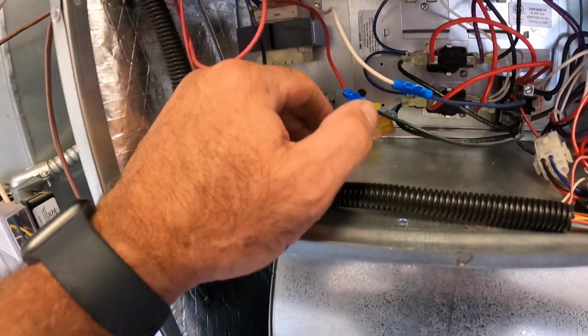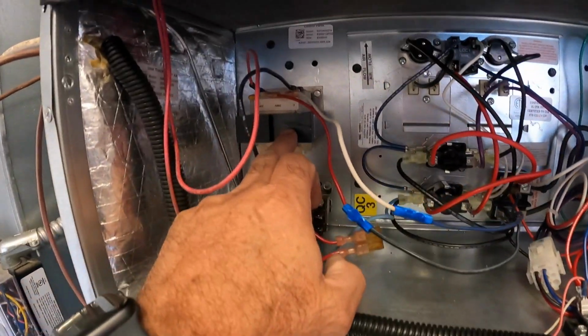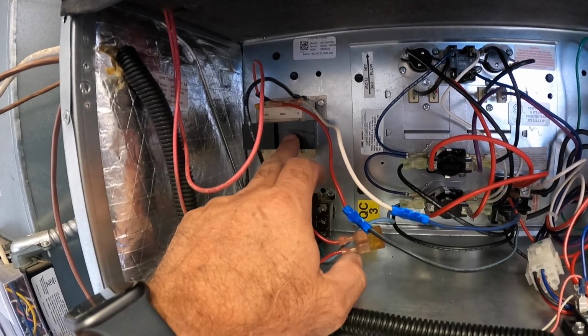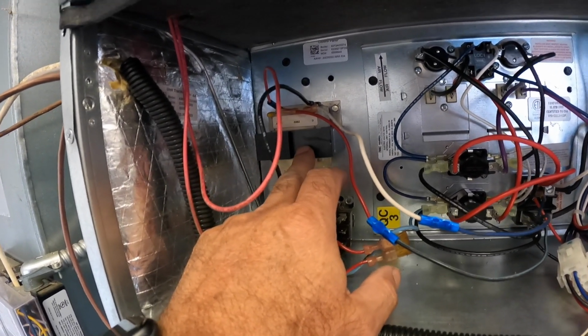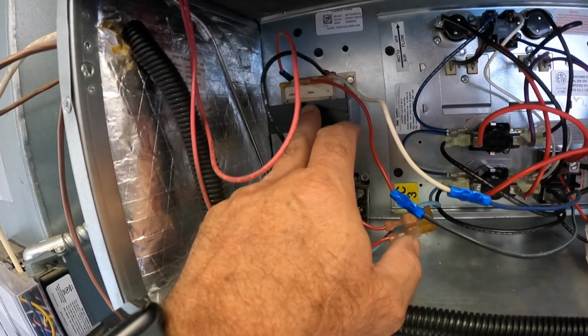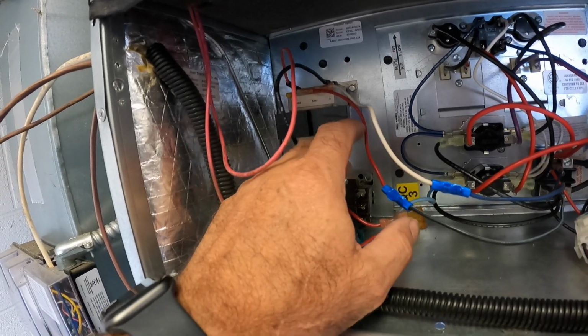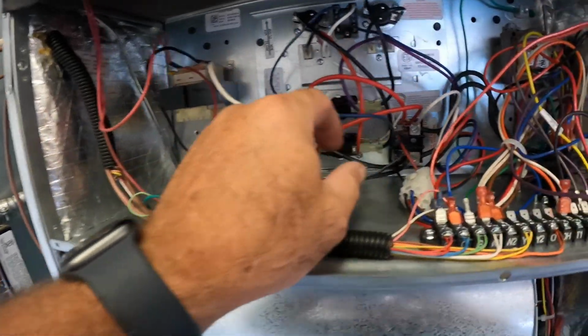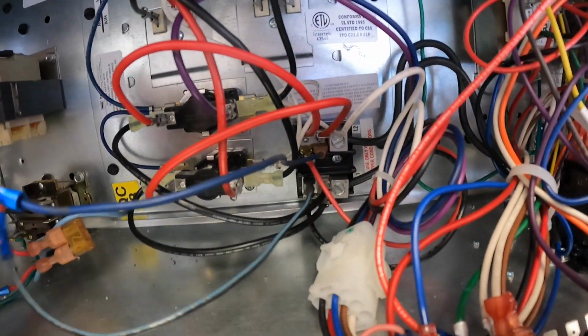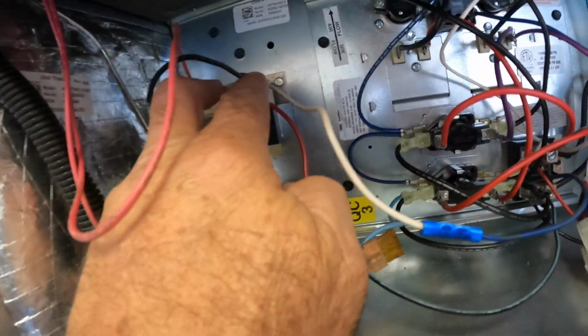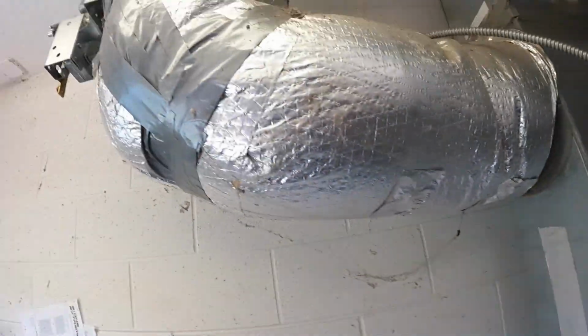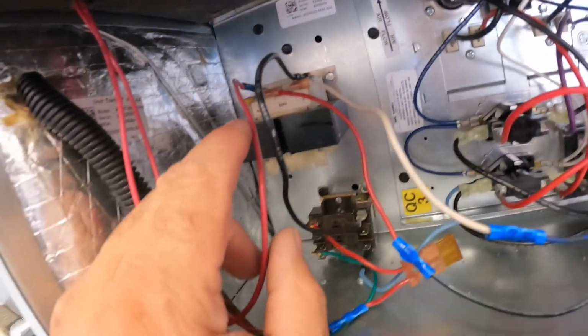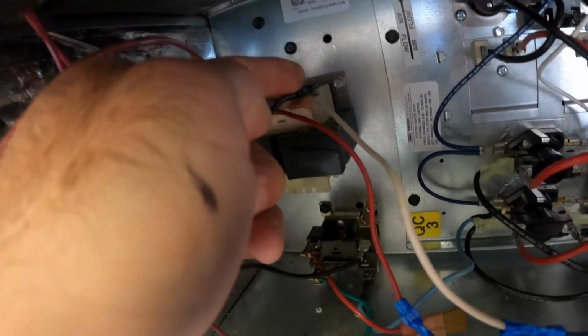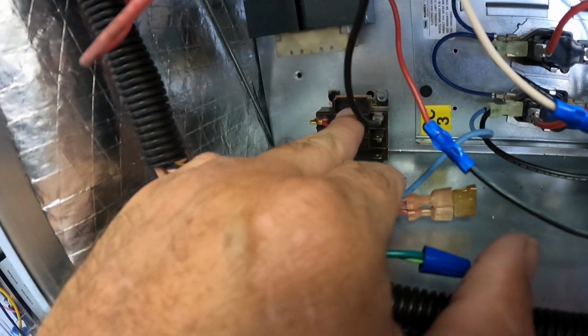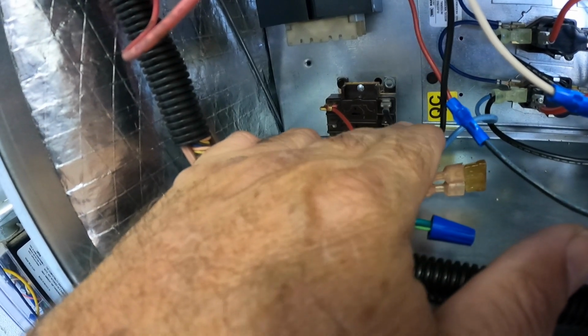Okay, I went ahead and finished up in here and got this fresh air damper rigged up. What I did, I took the control transformer out of the old Trane air handler, because it looked a lot better than that little one that Johnson Controls had put in there to start with that had never been used. It was already real rusty. So I just put it on over here. I had all this room. I tapped it off of my two main lugs, so I got 208 going into the 200 side of the primary here, and coming off of it, this one wire already had that crimped on terminal, so I just plugged it straight to the transformer on one side, and then I did a jumper from the other side of the transformer down to the fan relay out of the old air handler. Figure if it was turning that big motor on and off, it could probably handle this little damper.